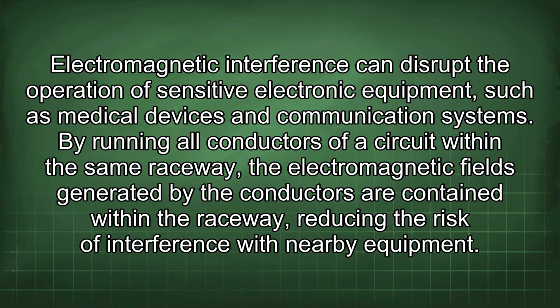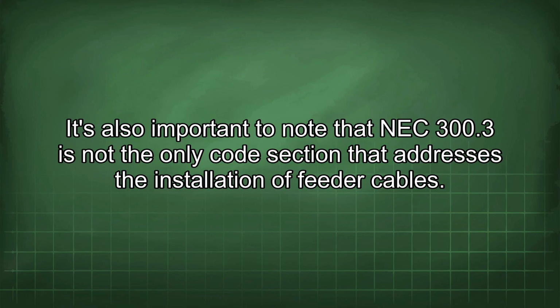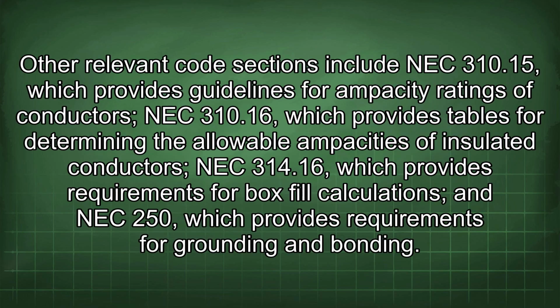By running all conductors of a circuit within the same raceway, the electromagnetic fields generated by the conductors are contained within the raceway, reducing the risk of interference with nearby equipment. It's also important to note that NEC 300.3 is not the only code section that addresses the installation of feeder cables. Other relevant code sections include NEC 310.15, which provides guidelines for ampacity ratings of conductors, NEC 310.16, which provides tables for determining the allowable ampacities of insulated conductors, NEC 314.16, which provides requirements for box fill calculations, and NEC 250, which provides requirements for grounding and bonding.